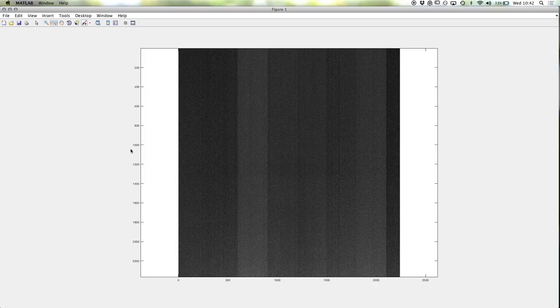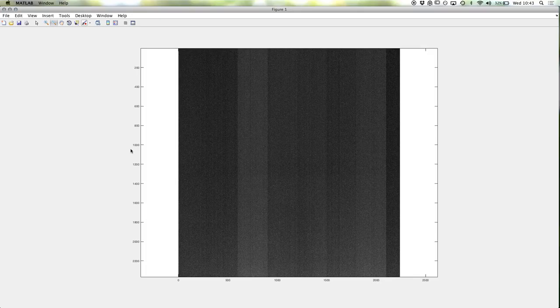This is something to be removed from the image — we need to calibrate for this different response of each pixel. We measure this image, and to average away noise what we do is record 100 images of this kind, so about 100 seconds — almost two minutes — letting the machine take 100 images like this and then average all of them. So this here is an average of 100 images, with the idea that in each pixel there is some random noise whose expected value is zero. After averaging we get a quite low-noise image revealing what each pixel is doing. For every x-ray image you measure later, you will subtract this one.